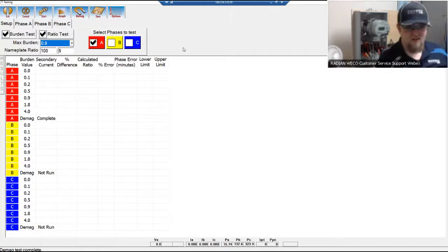To the right of that is selecting what phases you want to test for this run. You can test single phase and just do A, then do B, then do C. If you want to do 2 phases, you can do 2 phases. Or, like what I'm going to demonstrate here, you can do all 3 phases at once and run one test for all 3 phases of your CT. So if I check all of these, we're going to run all 3 CTs during one test.